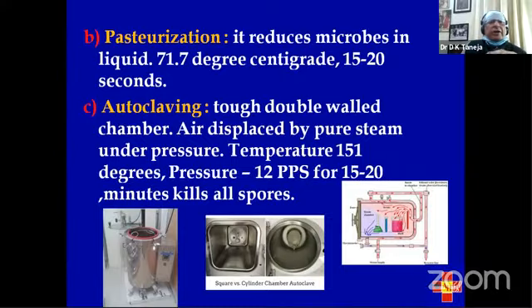Now, what is autoclaving? We have told you about the people who popularized this autoclaving system. It is a tough double-walled chamber, and in it the air is removed and then pure steam is introduced. Water is heated up, that water gives steam, and when there is pressure, it raises the temperature to 150 degrees. Therefore, under a pressure of 12 pounds, for 15 to 20 minutes, it will kill all the spores. That is the fundamental principle of autoclaving the instruments and the linen.